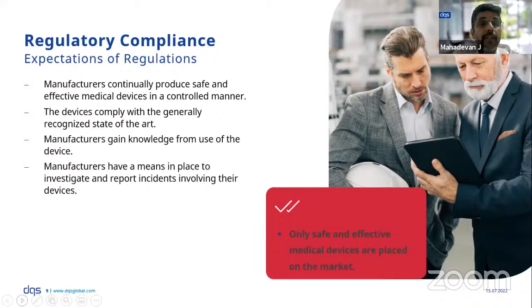Manufacturers must have a means in place to investigate and report incidents involving their device. So when you gain knowledge about your device, if there is any malfunction leading to any incidents, you need to report these incidents as per the applicable regulatory requirements. The bottom line is that only safe and effective medical devices are placed in the market. That is the fundamental goal of every regulator, so that only safe and effective medical devices are placed into the market.